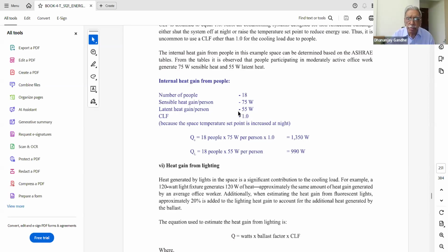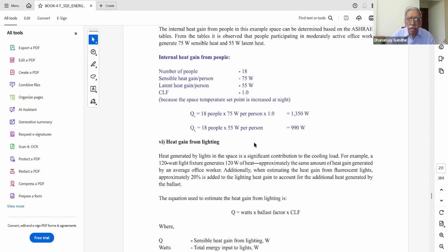And CLF is to be considered as one because there is not much variation over there. So the heat load calculation is 18 people, 75 watt per person is the sensible heat, and CLF is 1.0. So this works out to 1350 watt, and the latent heat gain from the 18 people is 18 multiplied by 55, which is equal to 990 watt.